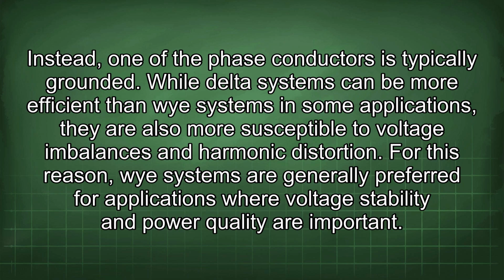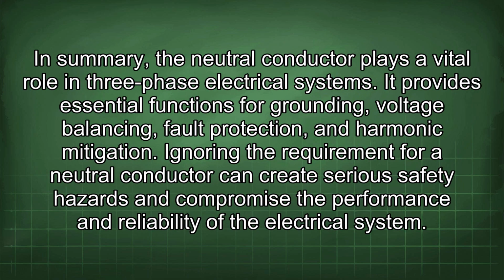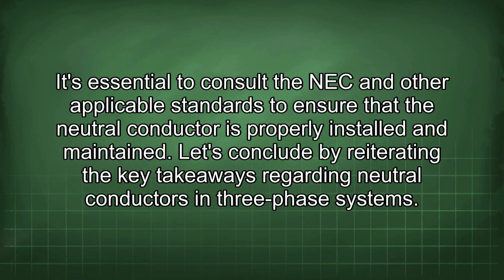In summary, the neutral conductor plays a vital role in three-phase electrical systems. It provides essential functions for grounding, voltage balancing, fault protection, and harmonic mitigation. Ignoring the requirement for a neutral conductor can create serious safety hazards and compromise the performance and reliability of the electrical system. It's essential to consult the NEC and other applicable standards to ensure that the neutral conductor is properly installed and maintained. Let's conclude by reiterating the key takeaways regarding neutral conductors in three-phase systems.